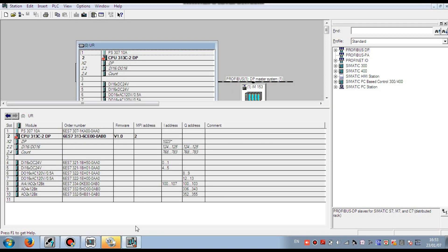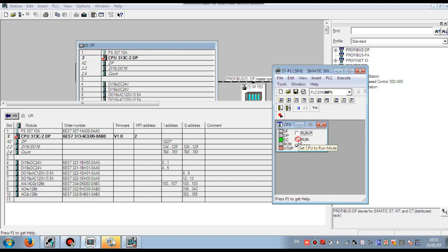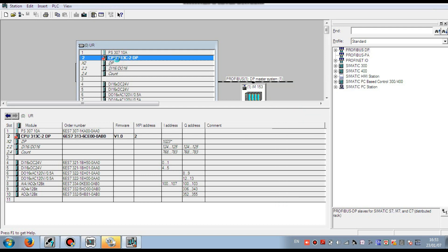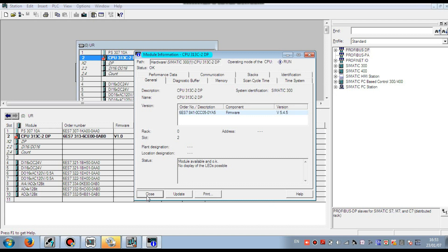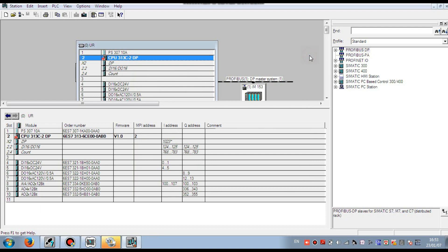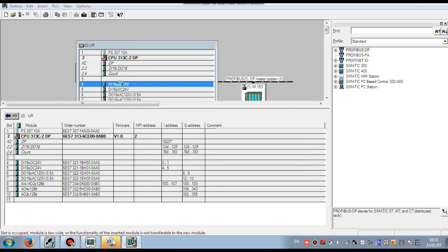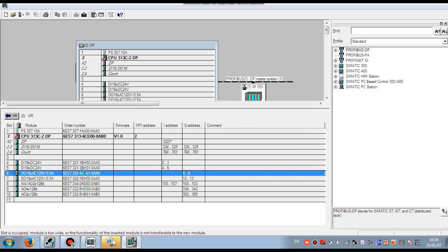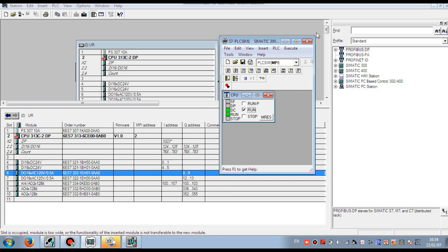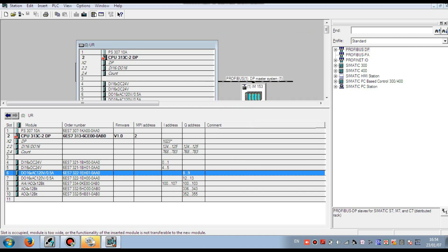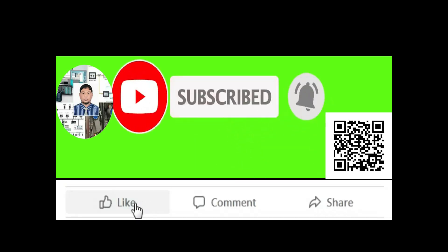Now go to Online — I want to see whether the modules are showing OK or not. It is going online. I press the CPU into Run mode, because in Run mode I can see the actual data of this hardware system. Go to the CPU and you see this module is available and OK. The status LED shows no alarm in this CPU — it is OK. All the other input/output cards I configured are also showing Module Available and OK. That means our configuration is 100% OK. In this way you can easily configure the hardware as per your requirement. If you like my video, please subscribe to my channel, press the Bell icon, like, comment, and share. Thanks for watching.